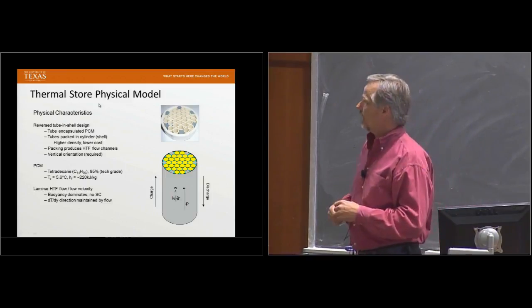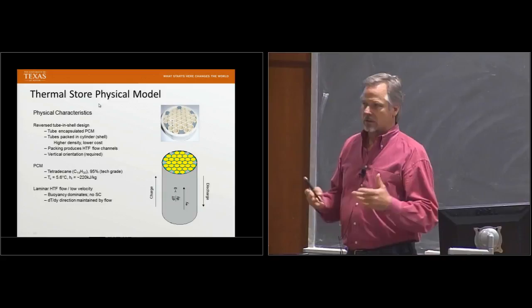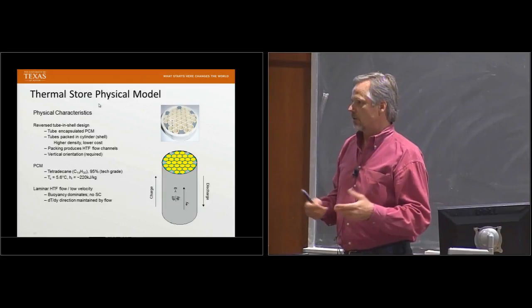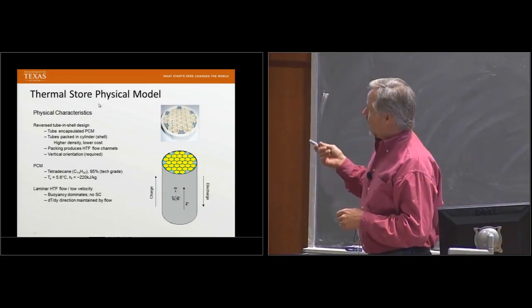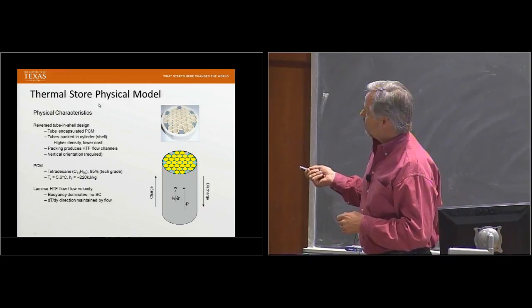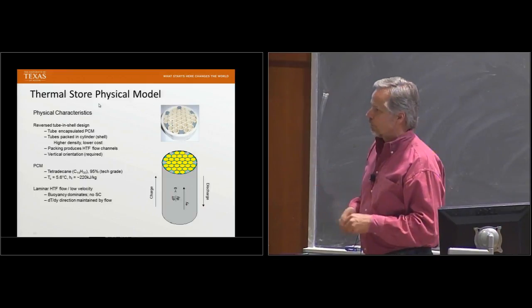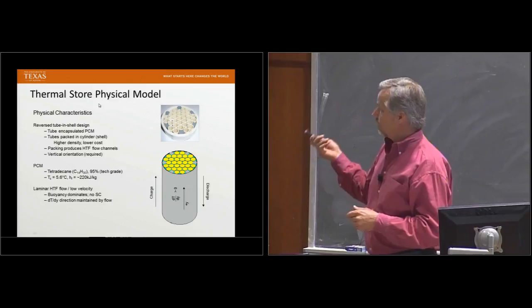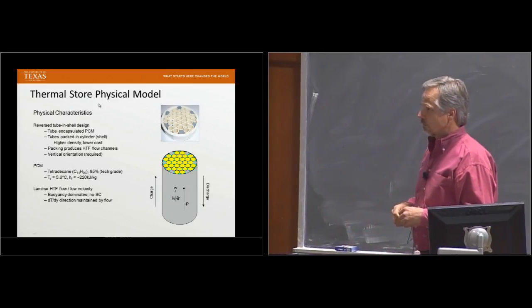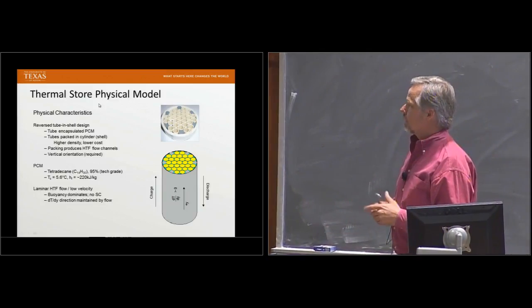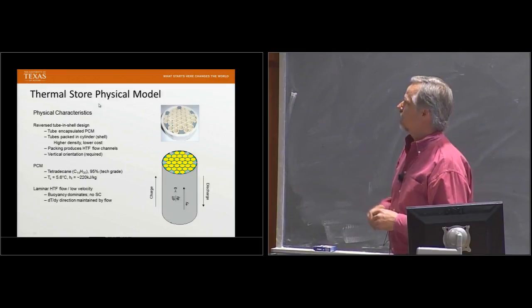paraffin called tetradecane. It's very similar to a light fuel oil. It has a freezing temperature we want of 5.6 degrees C, which is suitable for AC conditions, and it has a fairly large thermal storage rate of 220 kilojoules per kilogram during the phase change.